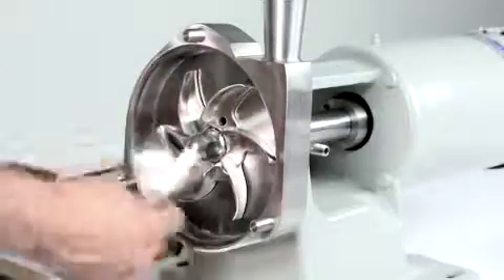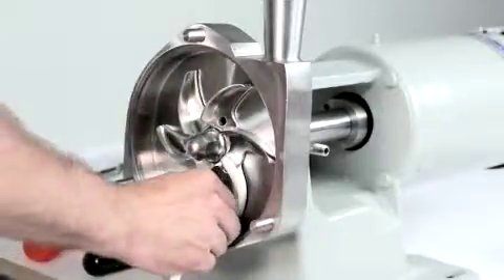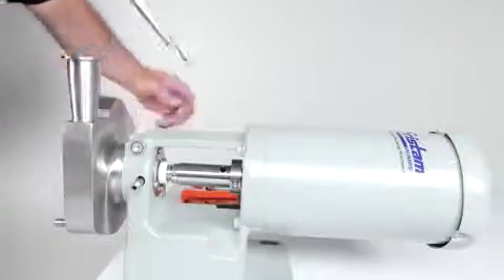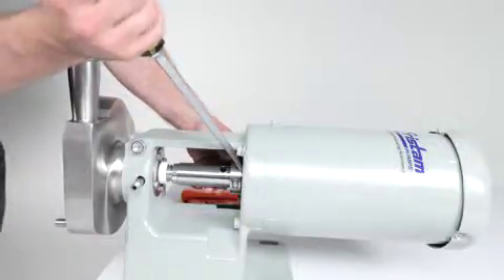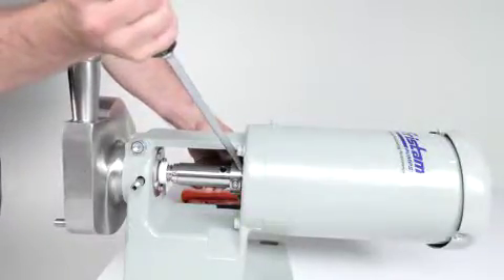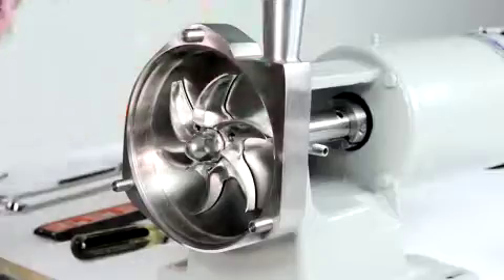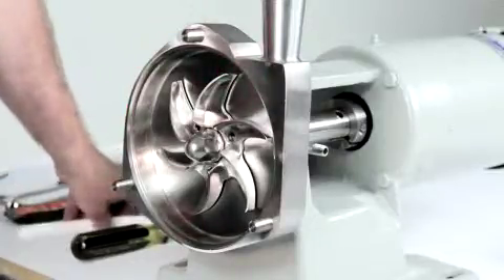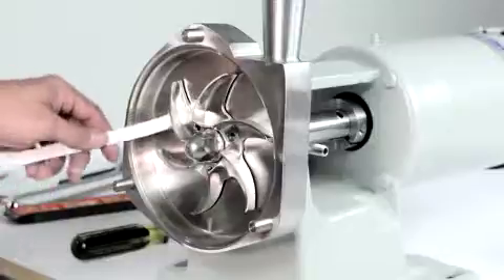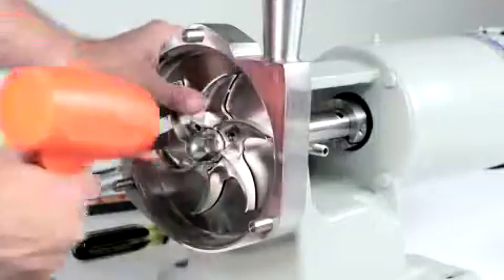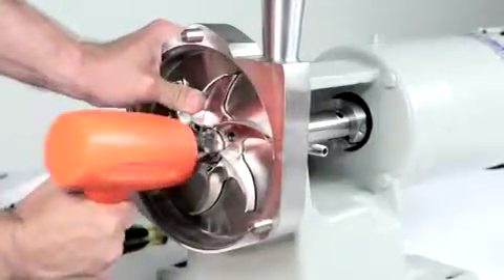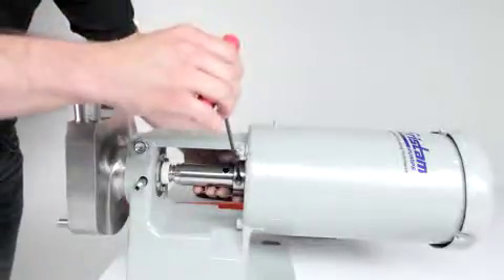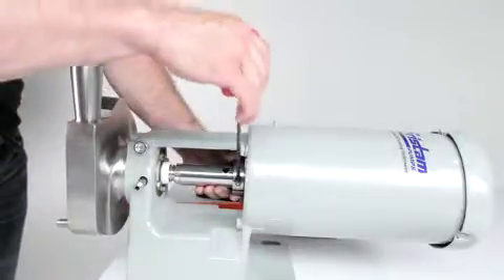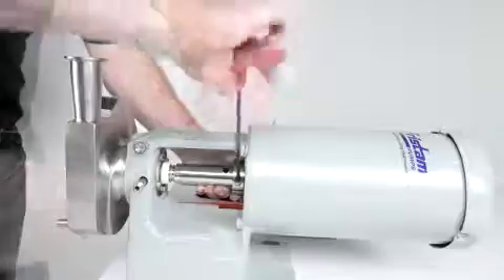The gap is measured between the impeller and pump housing using feeler gauges. With the shaft collar still loose, push the shaft slightly forward to leave room to adjust the gap. Place the correct feeler gauge behind two blades of the impeller. Using a soft-faced hammer, tap on the front of the impeller nut until the impeller is snug against the feeler gauge. Tighten the shaft collar screw on the shaft collar to the proper torque.